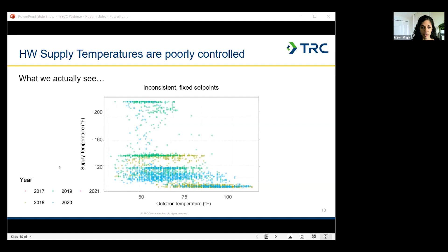This last example is one where it looked like there used to be good control, with some correlation between the supply temperature and outdoor air temperature. But at some point the set point was overridden to around 150, and since then the temperature's just been stuck there.